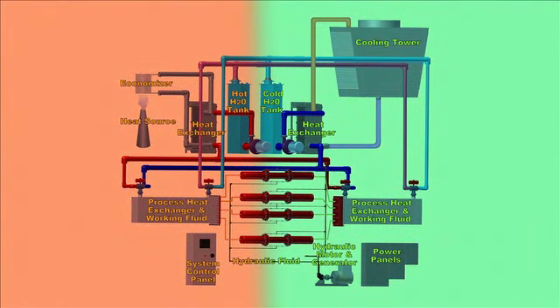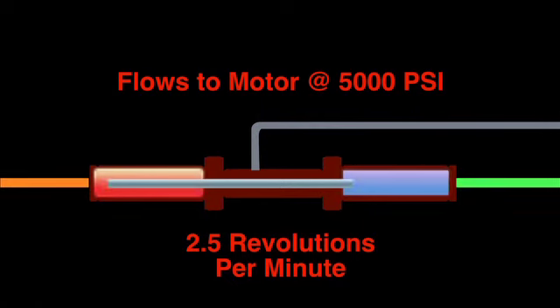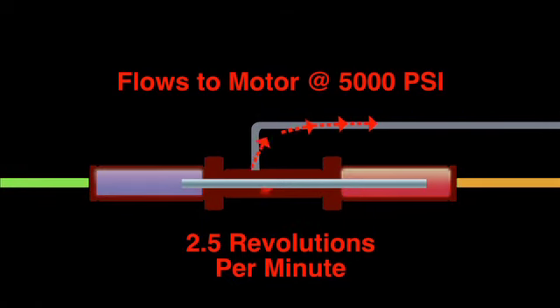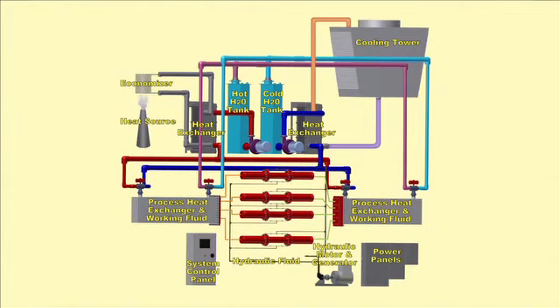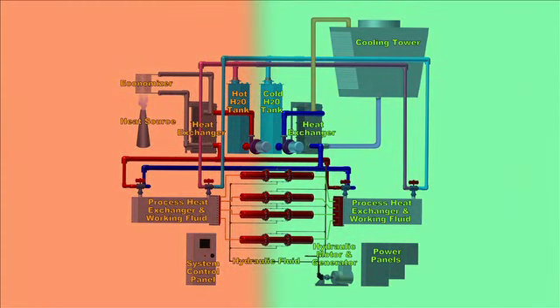At a specific time, a series of control valves change direction, and the heat exchanger, which was previously being heated, is now being cooled, and the previous heat exchanger being cooled is now being heated. This causes the triplex compounding cylinder assemblies to move back and forth to produce a laminar flow of hydraulic oil, which proceeds to a hydraulic motor. The hydraulic motor causes a generator to rotate at 1800 revolutions per minute, producing 480-volt three-phase power.